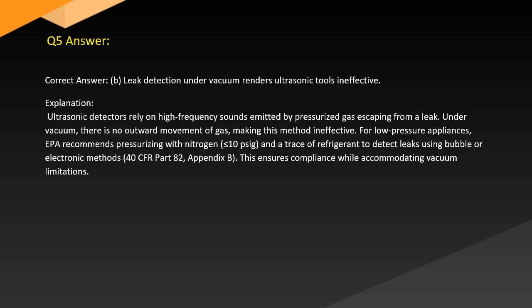Answer. Correct answer: B. Leak detection under vacuum renders ultrasonic tools ineffective. Explanation. Ultrasonic detectors rely on high-frequency sounds emitted by pressurized gas escaping from a leak. Under vacuum, there is no outward movement of gas, making this method ineffective. For low-pressure appliances, EPA recommends pressurizing with nitrogen to 10 psig and a trace of refrigerant to detect leaks using bubble or electronic methods. 40 CFR Part 82, Appendix B. This ensures compliance while accommodating vacuum limitations.